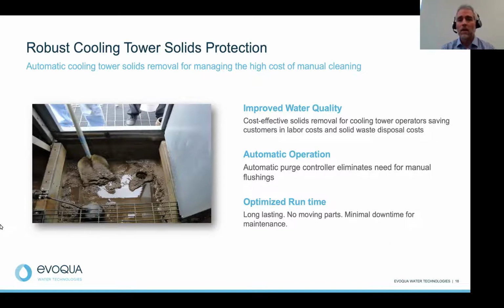This product is an automatically operated technology. We provide an automatic purge valve controller that allows the flush, or the discharge, of the solids down to your waste environment. No manual operators are required to go out and interact with the product or provide any type of manual cleanings. And this technology is really built for optimizing runtime, long lasting, heavy duty carbon steel, really no moving parts. So the separator itself has no moving parts within it. And this is really built for minimal downtime and very minimal maintenance.